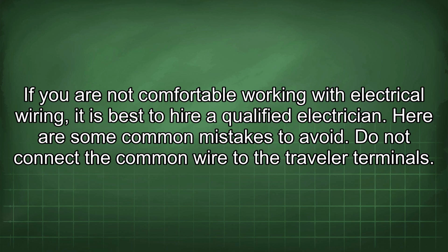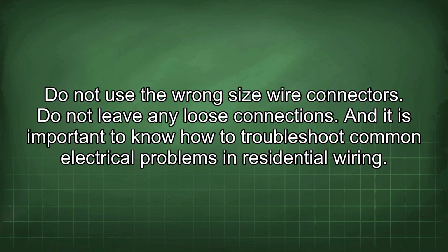Here are some common mistakes to avoid. Do not connect the common wire to the traveler terminals. Do not use the wrong size wire connectors. Do not leave any loose connections. And it is important to know how to troubleshoot common electrical problems in residential wiring.